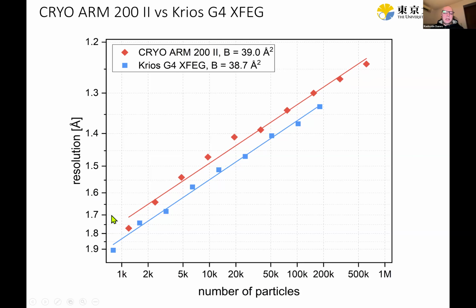And theoretically, this should be a linear plot. And you see it's very close to linear. So we did linear fits through these data points. And from the slope of this fit, we can actually measure the B factor. So for the CRYO ARM 200 II, the B factor was 39 angstrom squared.